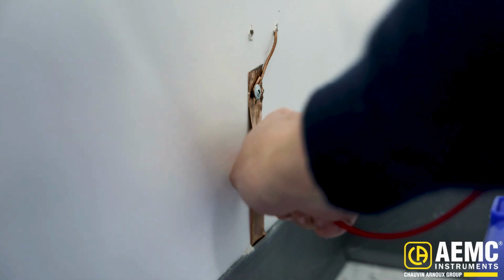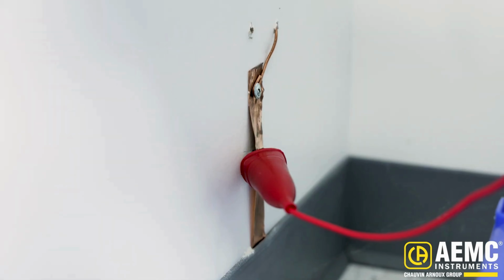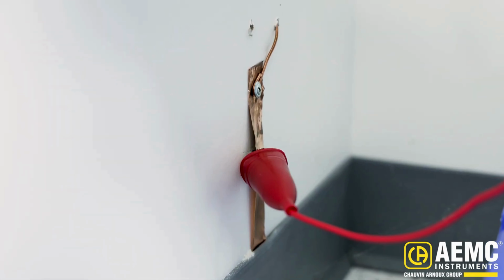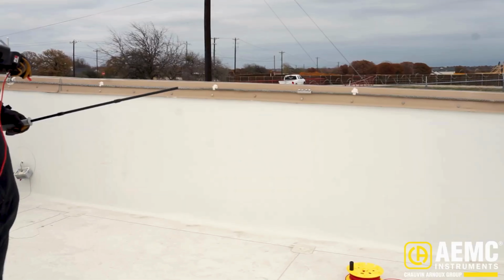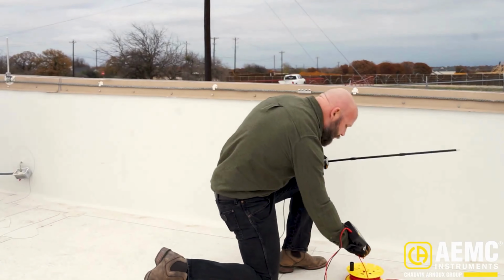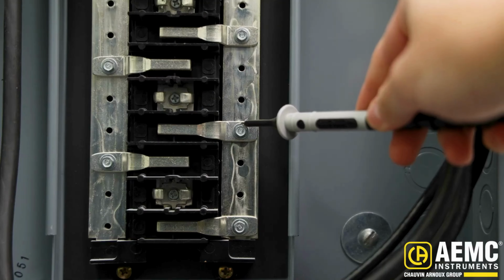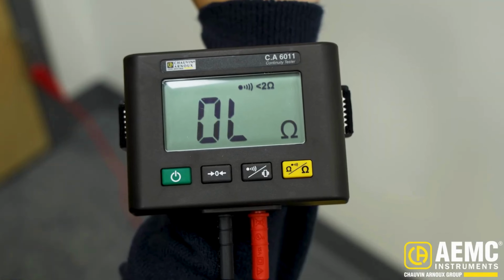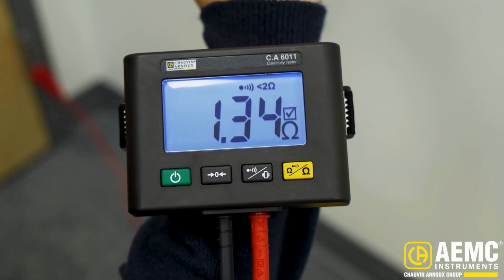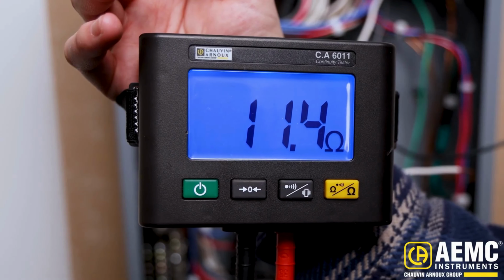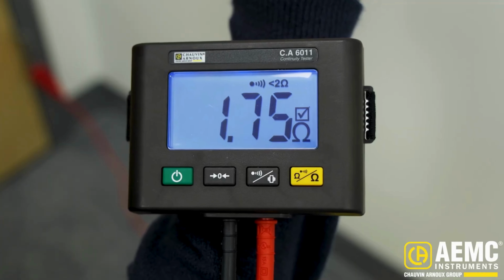Setup is simple. Clip the reel lead to your reference point, like the main ground bus or conductor, strap the display to your wrist, and walk the system with the continuity probe testing multiple contact points under test. When the instrument detects a low resistance path below your programmed threshold, the screen turns blue and you get clear visual, audible, and vibration indications, so you can confidently verify continuity in any environment.